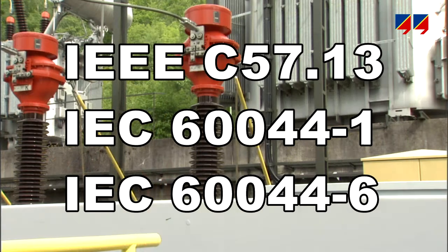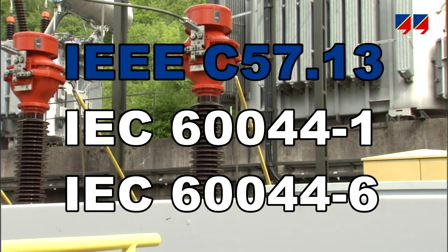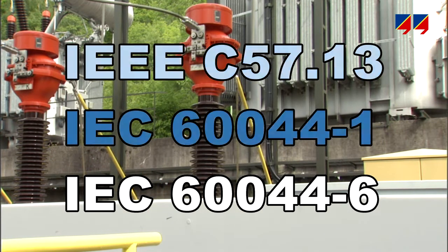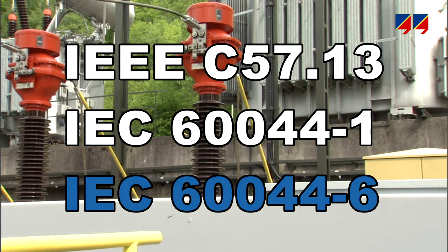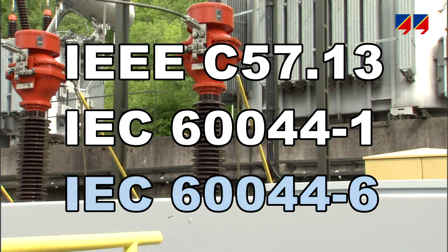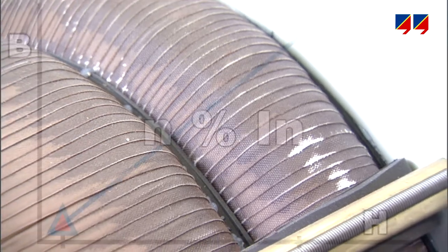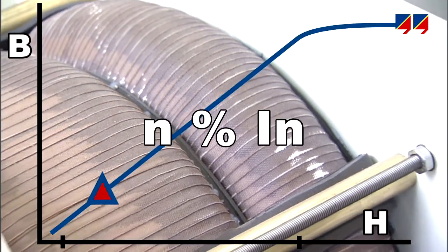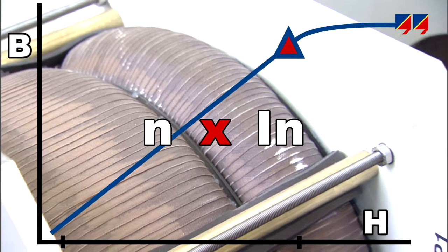International standards such as IEEE C57.13 and IEC 60044-1 and 60044-6 describe class characteristics of protection and metering CTs. Protection CTs have to transform currents from a few percent of nominal current up to many times its value during fault conditions.